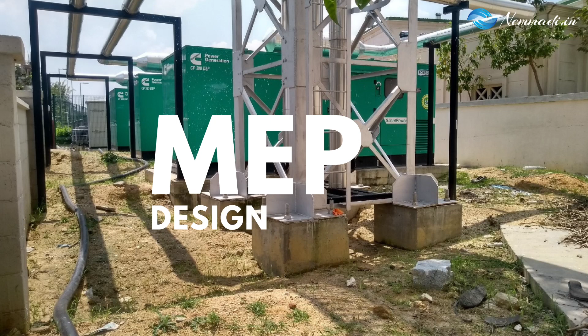Apart from this, we also do MEP design audits, checking whether the systems are adequate for the total occupancy of the apartment complex and whether they're serving the purpose. We do capacity checks — design audits for STP, transformer, UG sump, and DG set. For example, for the STP, as per the National Building Code guidelines, we draw out a water chart and find out whether the provided STP has sufficient capacity.